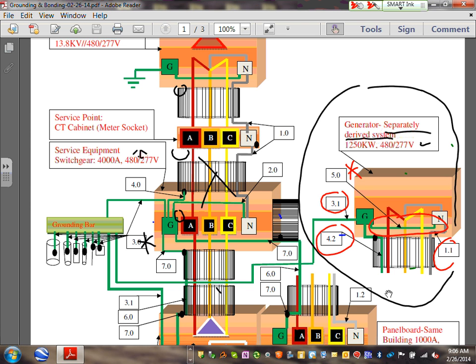Okay, now remember, this is a separately derived system. Now, Adam, if that was not a separately derived system, look what happened. The only thing that's going to be different here is, do you guys see that connection here? That number 5 is gone. If it's not a separately derived system, we just don't tie the neutral to the ground inside the generator. That's it. Number 5 is gone. Everything we calculate stays the same, but number 5 is gone.